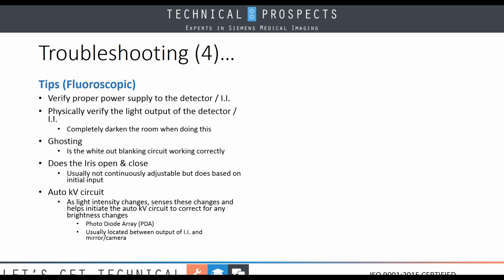But can it adjust? That's an important factor because that first pulse may be at different levels and stuff. So something we should be verifying, does our iris open and close with that? And of course, the auto KV circuit, and we talked about this earlier. All right, as the light intensity changes, this is what adjusts our KV, photodiode array. All right, in our modern circuits.